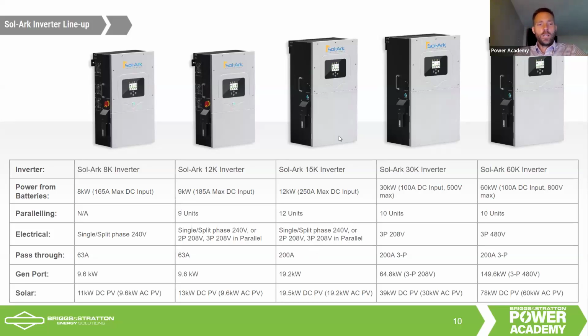It's got 200 amps of pass through, and this is the big game changer here compared to the 12K. So both the 8 and the 12K only have 63 amps of pass through, and so it's difficult to back up a common home even when it's a 100 amp service. Do a complete home with a Sol-Ark 12K, but with a 15K, having the ability to pass through 200 amps, having the ability to produce 12 kilowatts from the batteries to back that home up during an outage is a pretty big game changer.